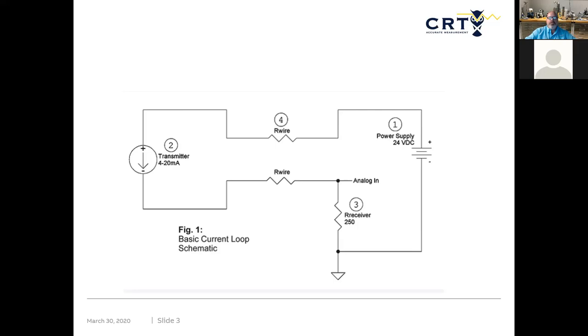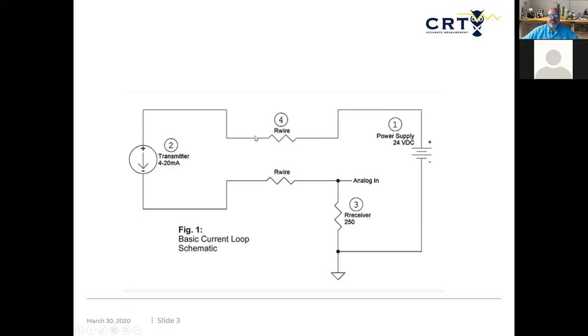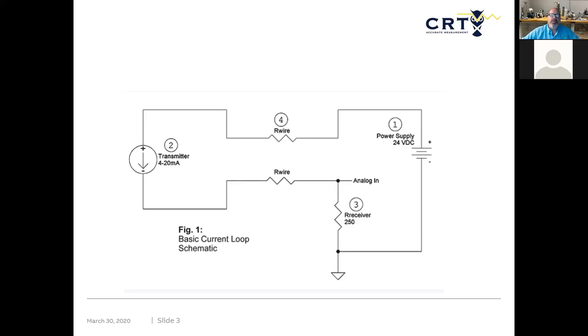So what we do is when we put a transmitter into this loop, we have resistance of the wire. I've got a power supply, and I'm sending voltage out. When I go through the transmitter, I'm basically going to change the resistance based upon the process signal that I'm sending out, and then that loop comes back, and then I measure that circuit, and determine what the milliamps are on that circuit.